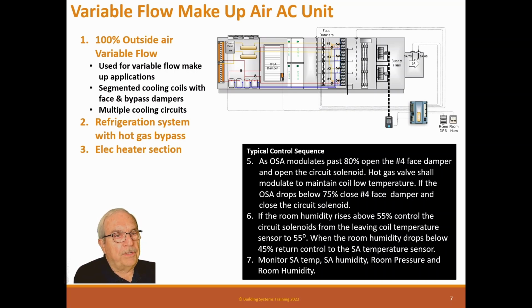If the room humidity rises above 55%, control the circuit solenoid from the leaving coil temperature sensor to 55 degrees. When the room humidity drops below 45%, return control to the supply air temperature sensor. Monitor the supply air temperature, supply humidity, room pressure, and room humidity.